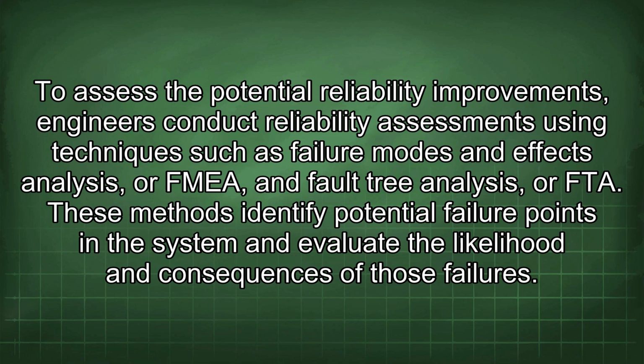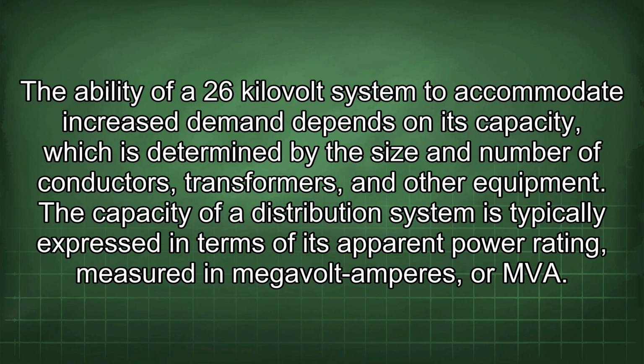These methods identify potential failure points in the system and evaluate the likelihood and consequences of those failures. The ability of a 26 kV system to accommodate increased demand depends on its capacity, which is determined by the size and number of conductors, transformers, and other equipment.